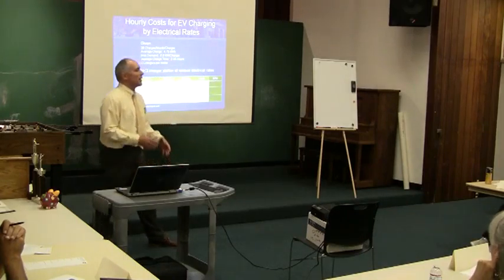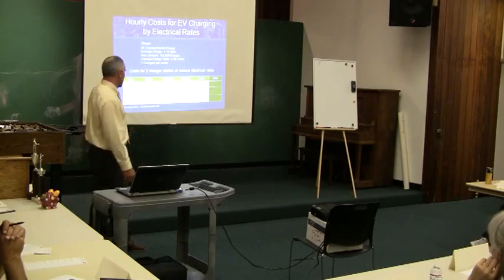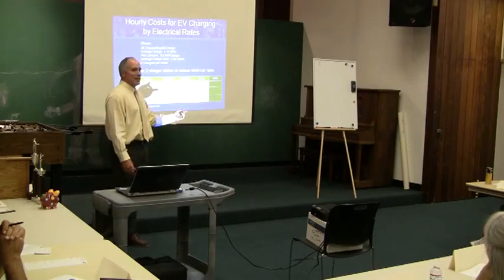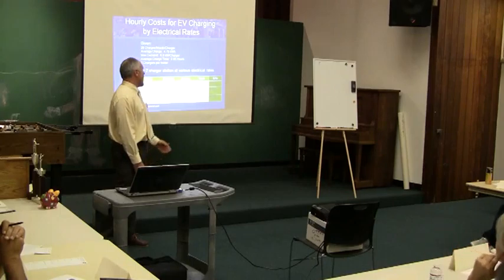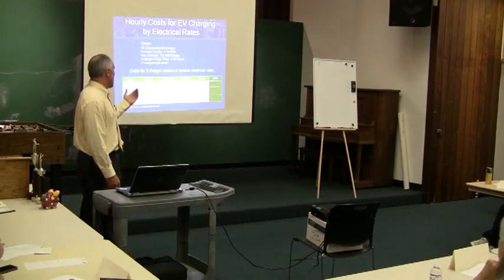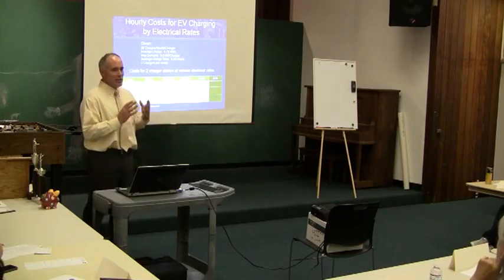So we're really just recovering our cost when we charge $1 an hour on average. Now on the GS2 tariff that we have at Granada Garage, our demand cost is pretty steep. Okay, so that's set by the Teslas, and it's about $250 a month. And overall, that averages out to a total cost of about $2.50 an hour. So you can see that we would much rather prefer to be on the EV3 tariff than the GS2.